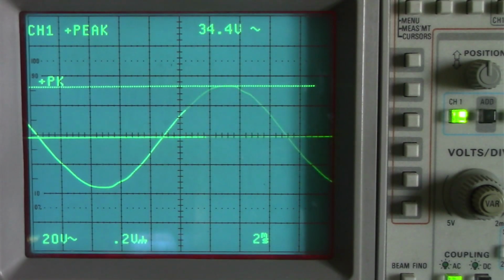And now we move to the oscilloscope to see those voltage and current waveforms. At this moment in time, I have channel 1 set to 20 volts per division, and I've got the cursors on, so you can see that the peak of that waveform is about 34 volts. Why 34? Well, it's a 24 volt transformer. 24 times root 2 is about 34. So we've taken that 24 volt RMS and converted it into a peak voltage. We've set the variac to provide that peak voltage into the 24 volt winding of the transformer.